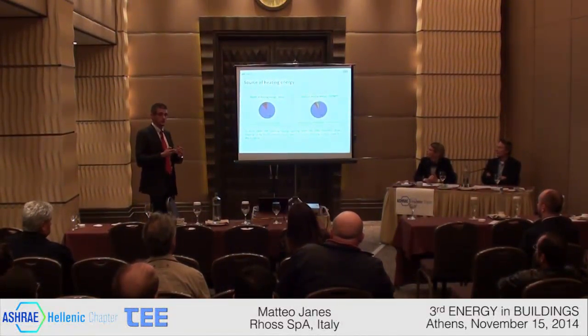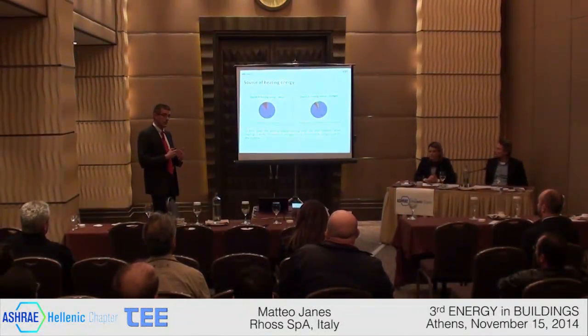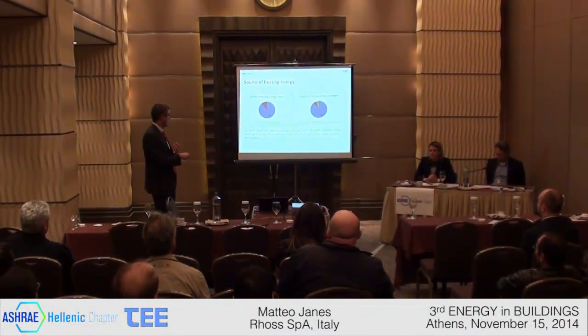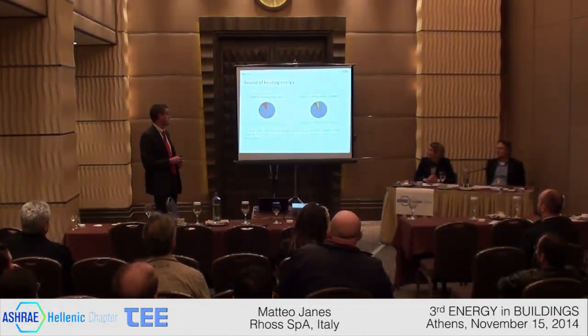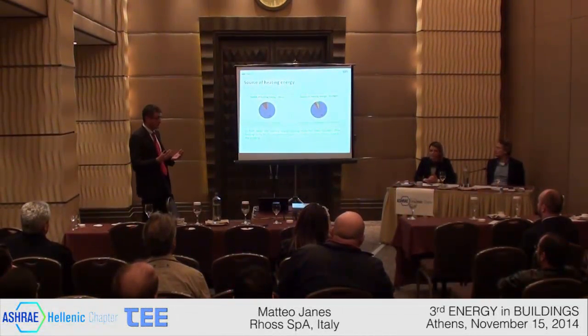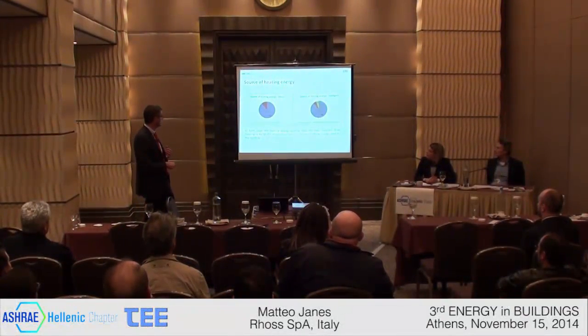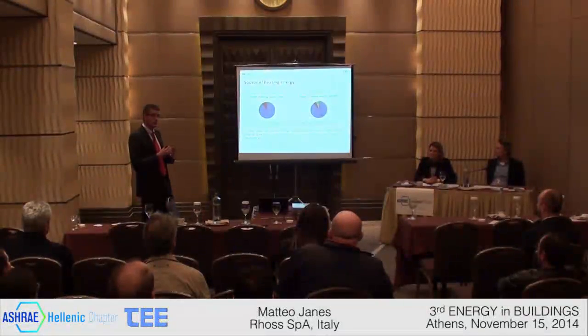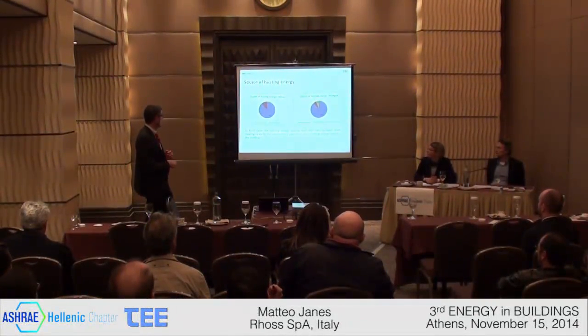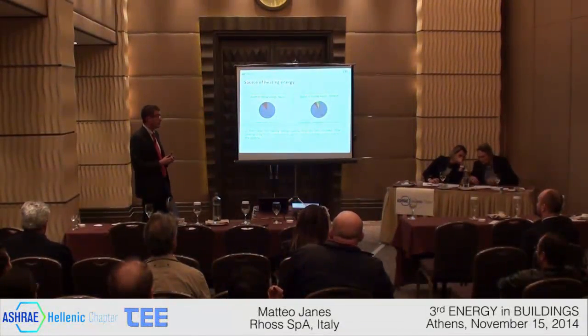If we look at the source of the heating energy used by the building, both in Milan and in a much colder city, Stuttgart in Germany, during the whole year, we can see that the biggest part of the heating energy, around 90%, comes from the heat recovery, which means it's for free. Only a small amount of that energy comes from the heat pump, so we have to pay for that in the case of Milan, or from an external source, the boiler, in the case of Stuttgart.